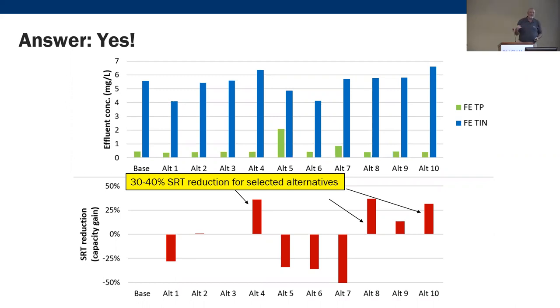So let's try them out. What's the benefit of SRT reduction? That's less solids we have to satisfy with oxygen demand — less biomass we have to keep alive. The model tells us we're not jeopardizing water quality, but we've actually decreased oxygen in some zones and decreased the SRT. That's a serious change in energy usage right there.